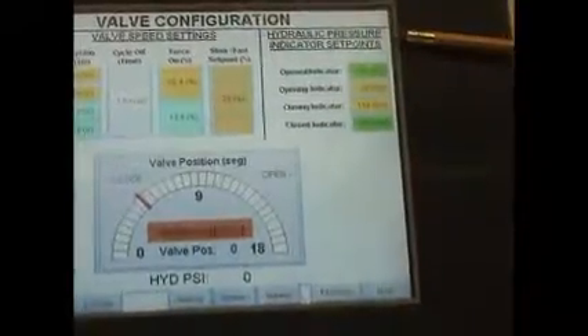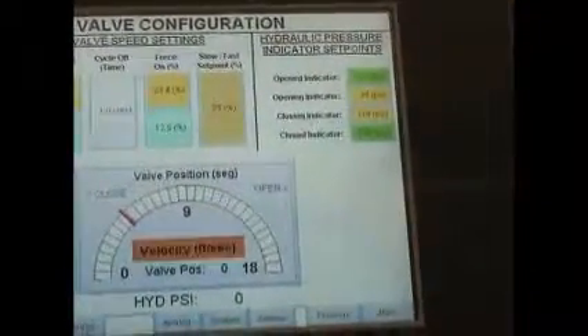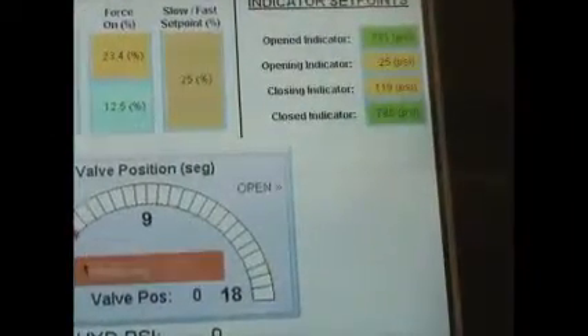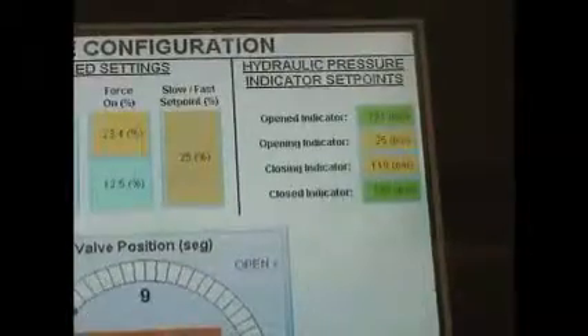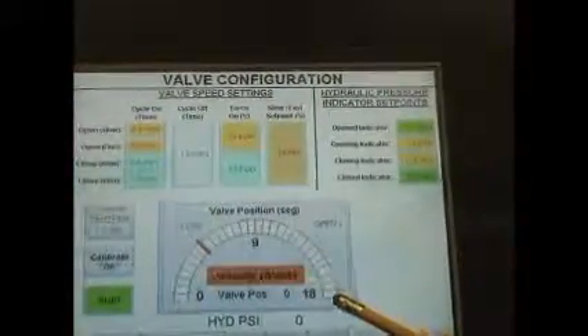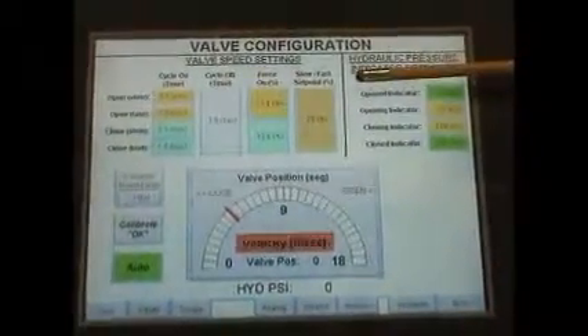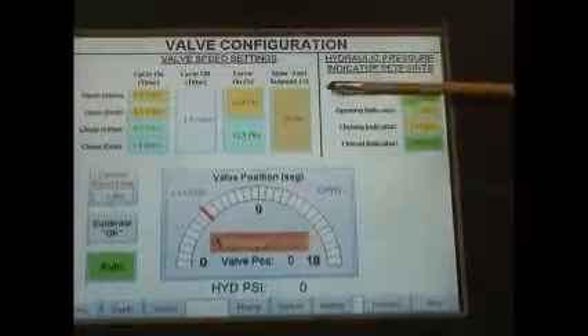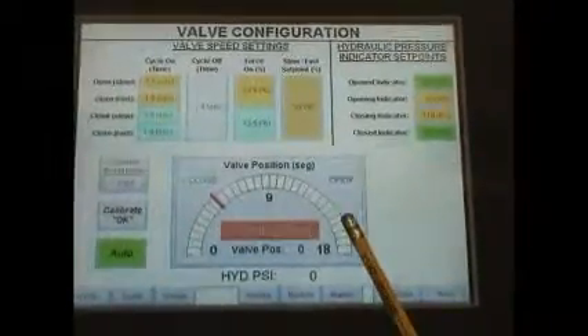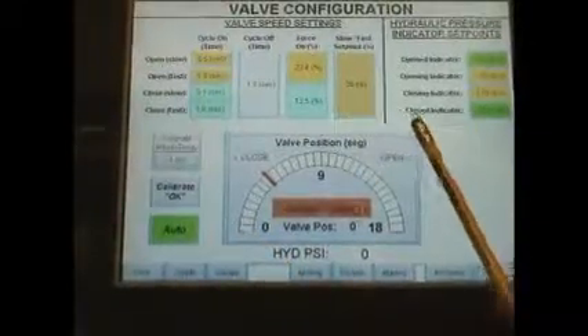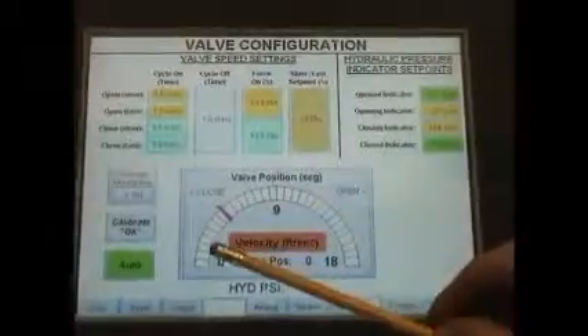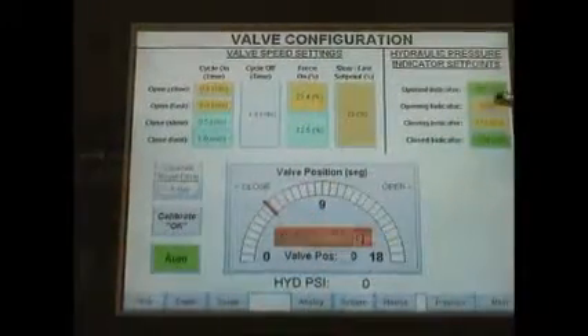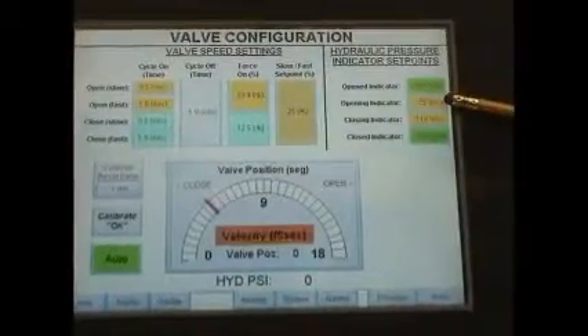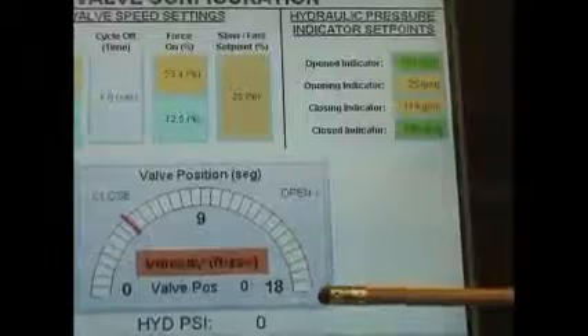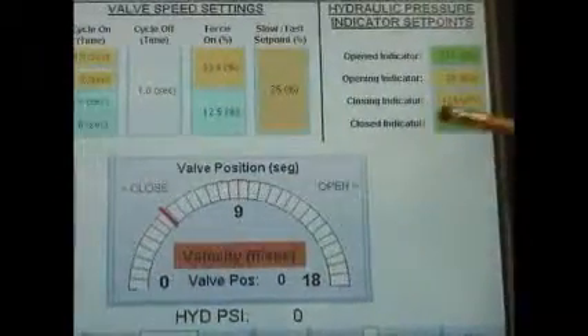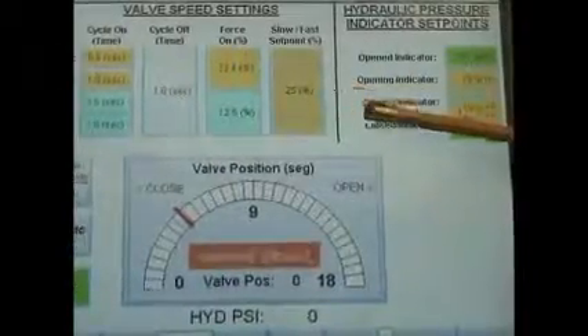Next we have our hydraulic pressure indicator set points. These are the pressures that the computer puts in there when it goes through a calibration process. The first thing in a calibration process is the valve fully opens up all the way and records its relief pressure. It puts this in right here, the opened indicator, or the open relief pressure. The next thing the valve does is fully close and record the closed indicator pressure. Then it starts stepping itself open. That step open process during the calibration records what the pressure is during the step open. When the valve reverses itself and starts to step closed, it records the closing set point pressure.